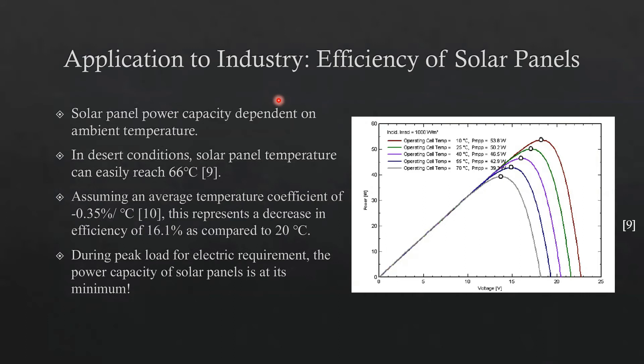One of these inefficiencies is the dependency of efficiency on solar panel surface temperature. In this graph, we see that at 70 degrees C, we have roughly 40 watts of output, whereas at 10 degrees C, we have 54 watts of output. Looking at the worst case scenario — a desert climate where temperature and solar irradiation are at their maximum — the solar panel surface temperature can easily be 66 degrees C or more. Compared to 20 degrees C, using an average temperature coefficient, that gives us a 16% decrease in efficiency.